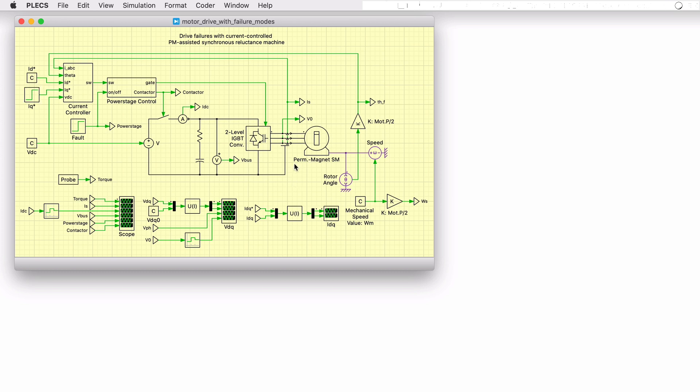the rectified back EMF is larger than the DC link voltage. Simply disabling the power stage would result in an uncontrolled current flow from the machine into the battery and an uncontrolled braking torque on the load. A fault mitigation strategy for this situation will be required to prevent this unregulated power flow into the battery.